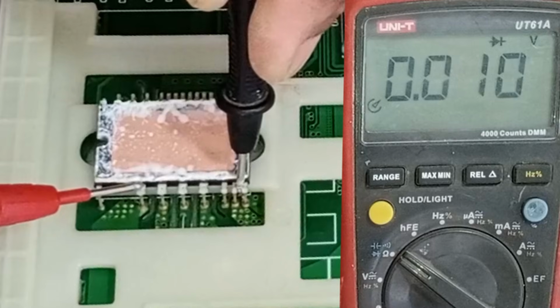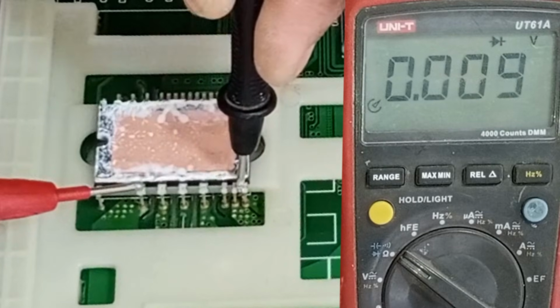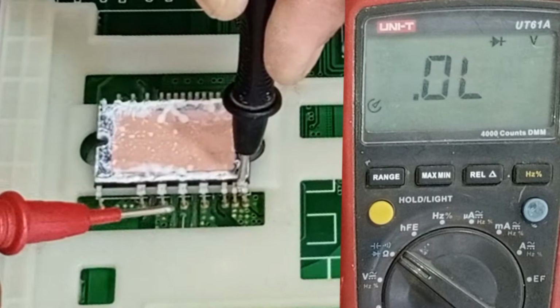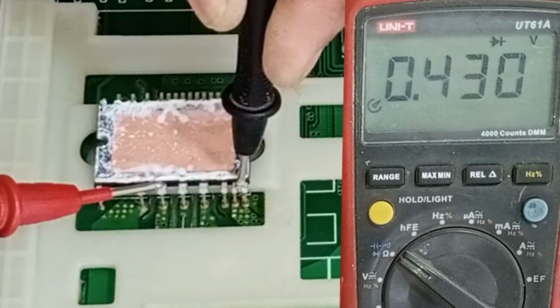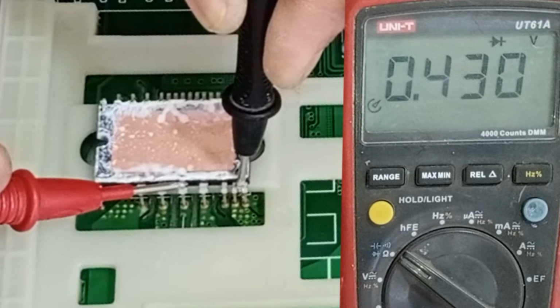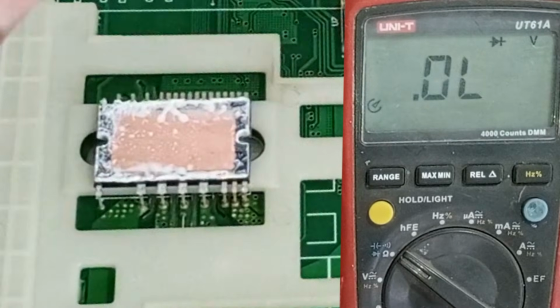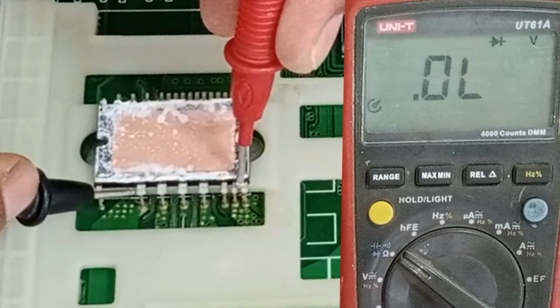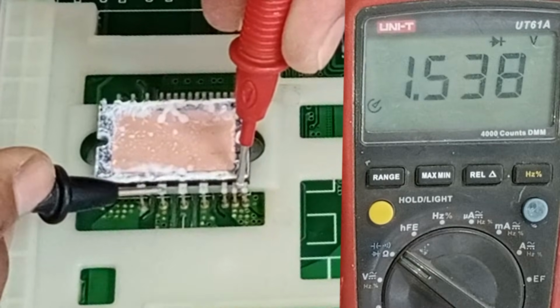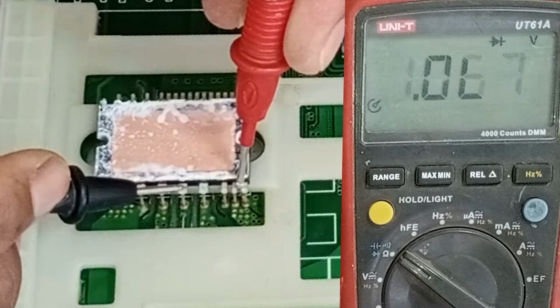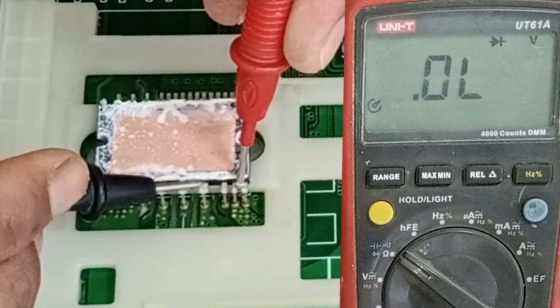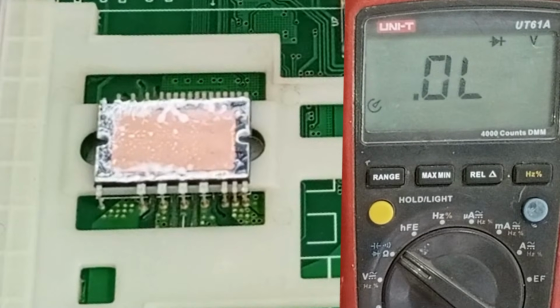Moving to the second pin, the voltage drop is showing 0, which is unusual. Let's check the next pin, where the voltage drop is displayed. The third pin also shows a voltage drop reading. Now I'll reverse the probes and check again. The second pin still shows 0 voltage drop, while the third, fourth, and fifth pins display a voltage drop. This suggests that the IPM might be shorted.